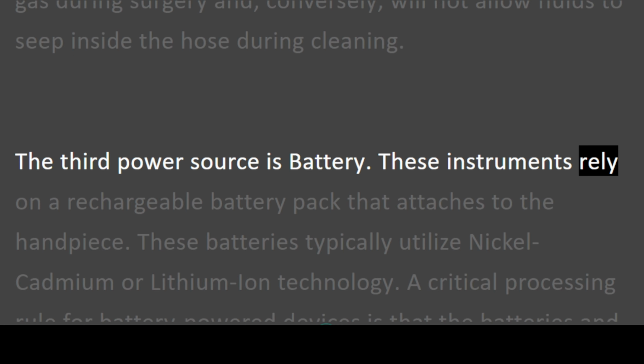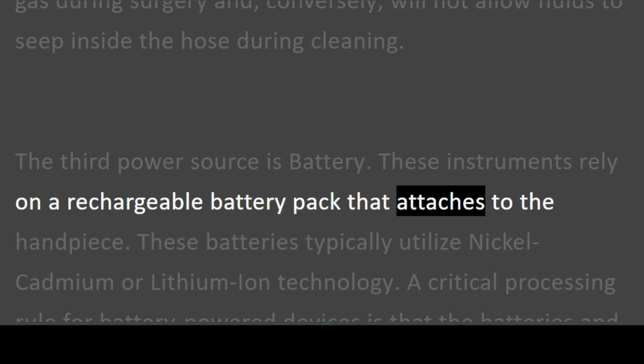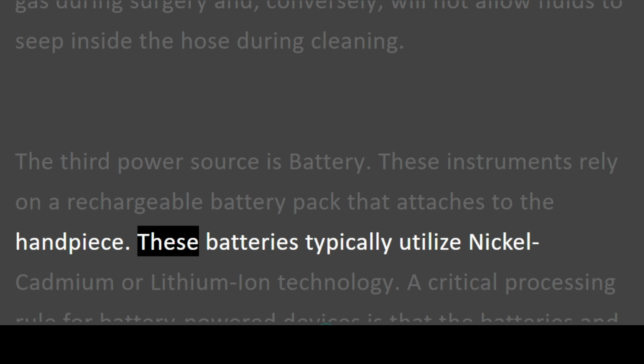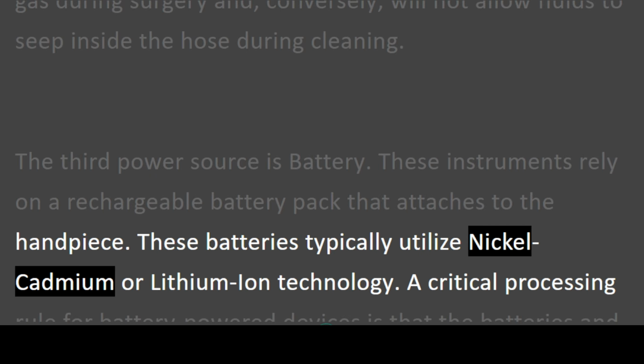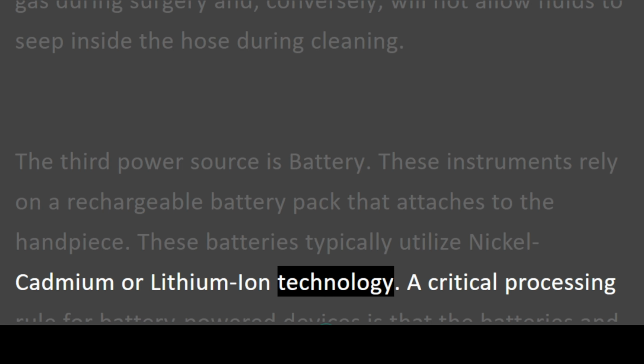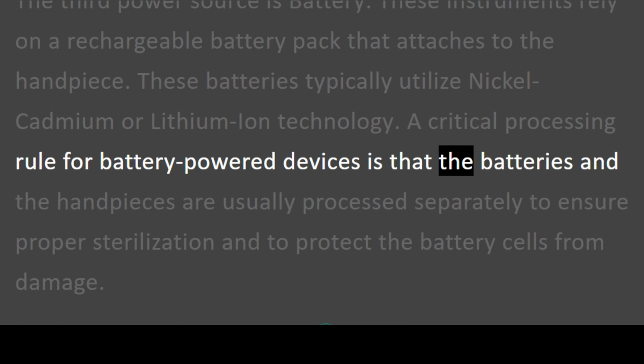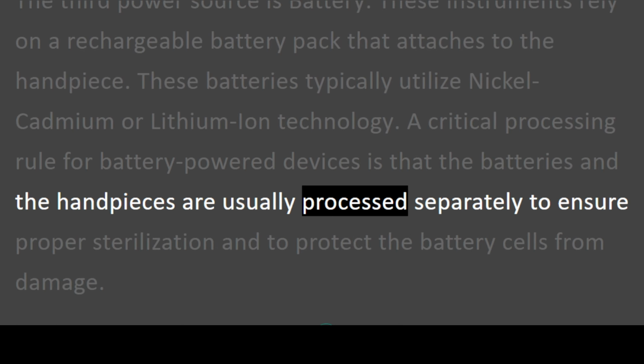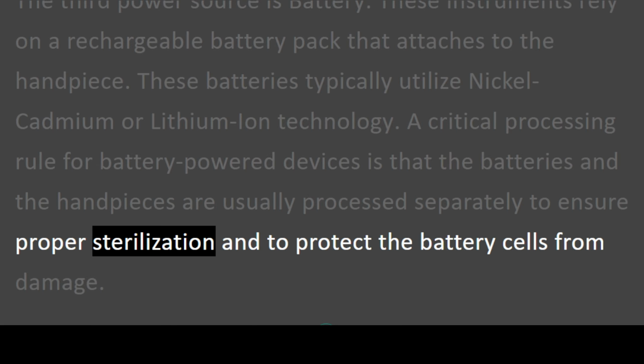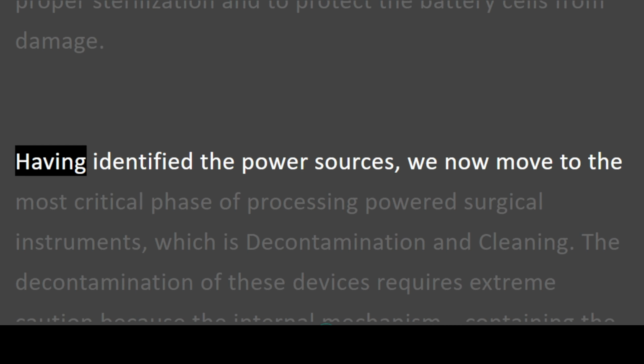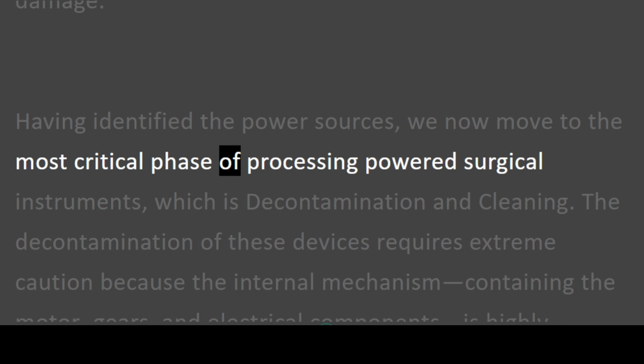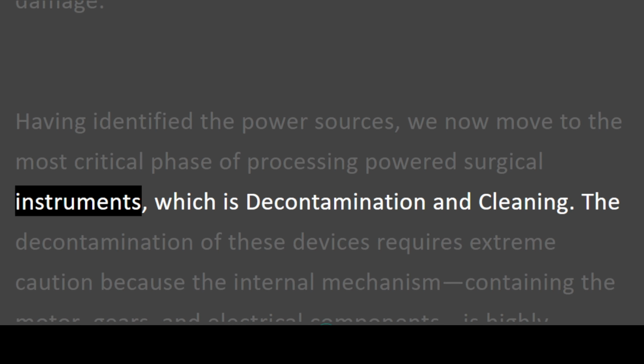These instruments rely on a rechargeable battery pack that attaches to the handpiece. These batteries typically utilize nickel-cadmium or lithium-ion technology. A critical processing rule for battery-powered devices is that the batteries and the handpieces are usually processed separately to ensure proper sterilization and to protect the battery cells from damage. Having identified the power sources, we now move to the most critical phase of processing powered surgical instruments, which is decontamination and cleaning.